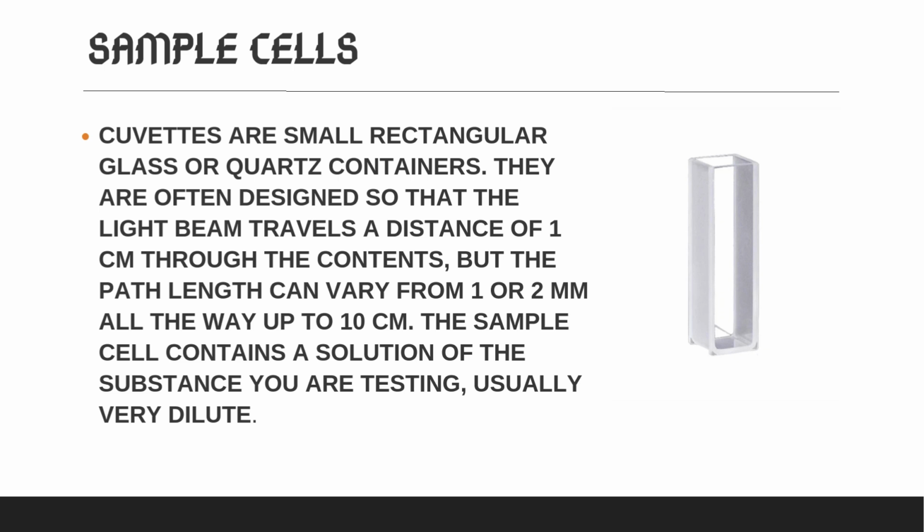In a fluorimeter, sample cells or cuvettes are used to hold the samples during fluorescence measurement. Some key characteristics of sample cells are: material of sample cells is quartz or optical glass, which allow UV visible light to pass through without absorbing it.